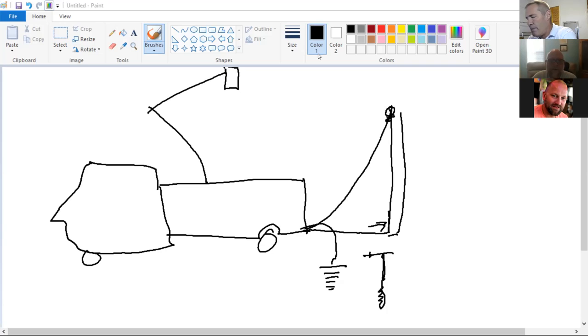It's mandatory, gentlemen: this ground cable is coiled up in the bed of the truck, or sometimes in a little tray or bin at the bottom. When you take it out, you don't just pull out a certain amount of feet, say 4, 5, 6 feet, attach it and leave the rest coiled in the truck. You've got to stretch it completely out on the ground and come back and attach it to the ground rod. You cannot leave it in the coil, either on the ground or on the truck.